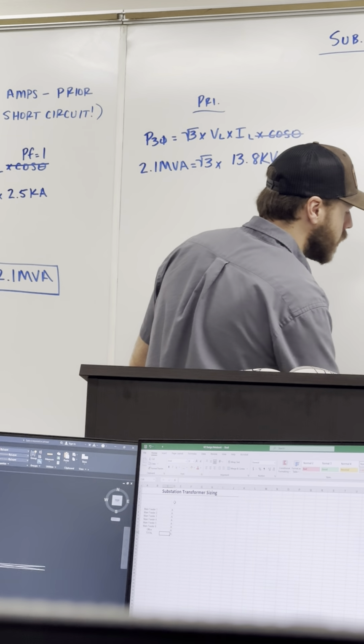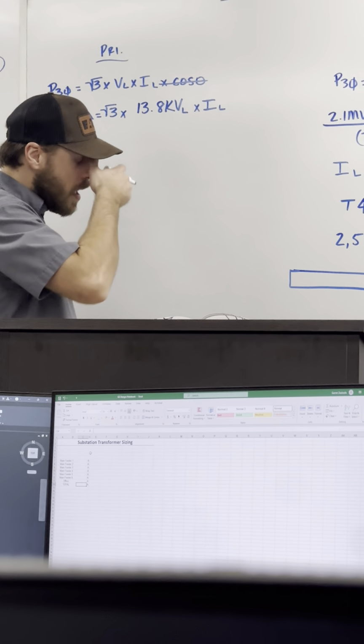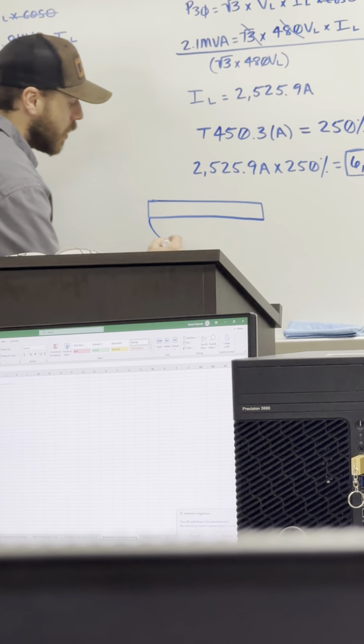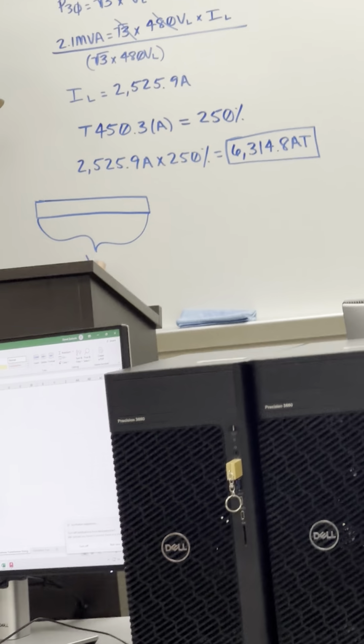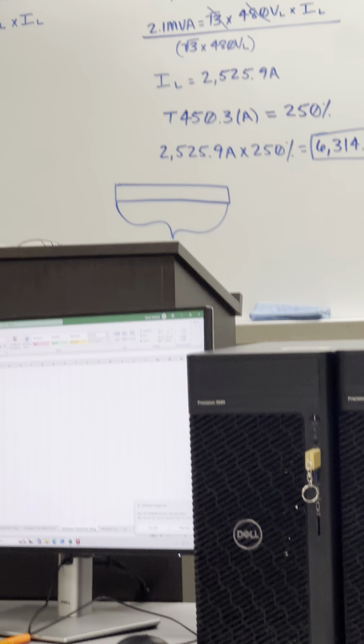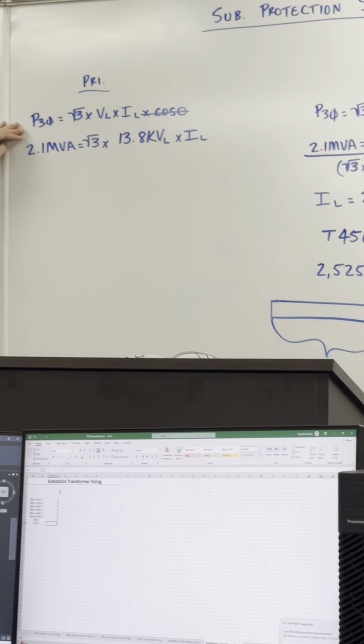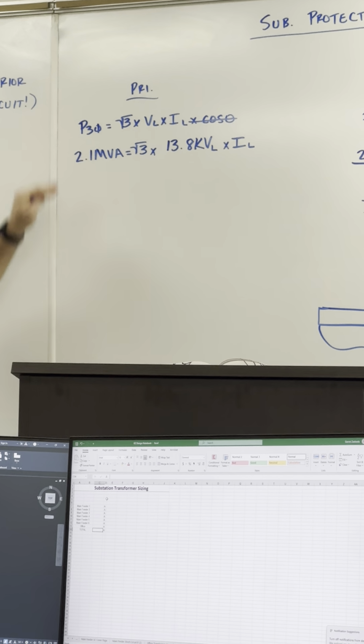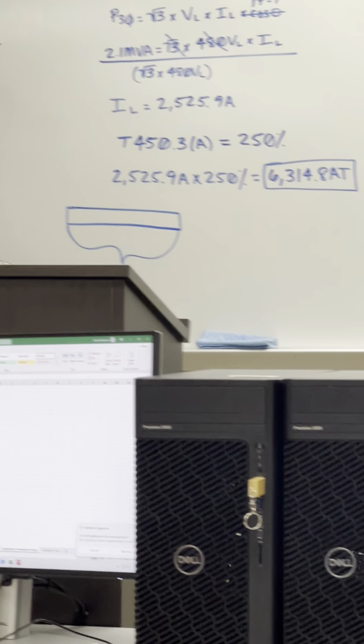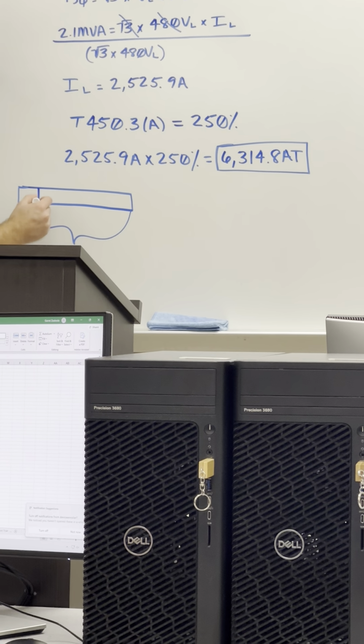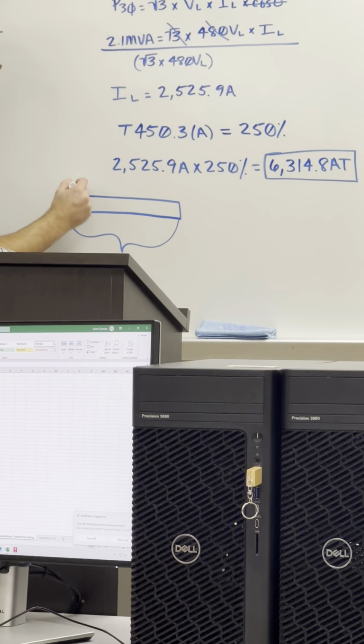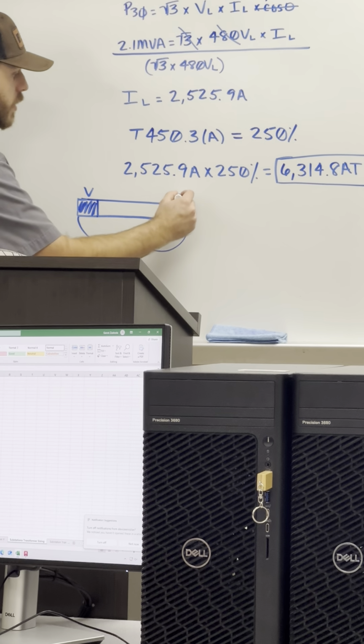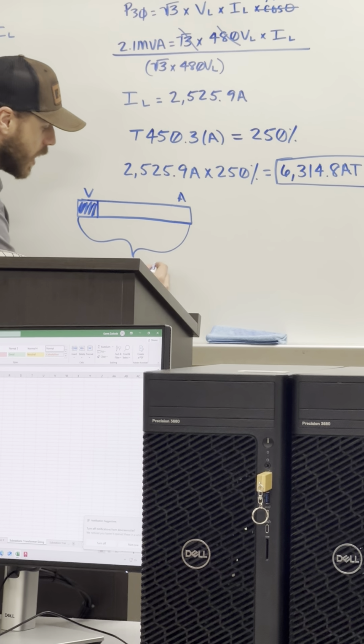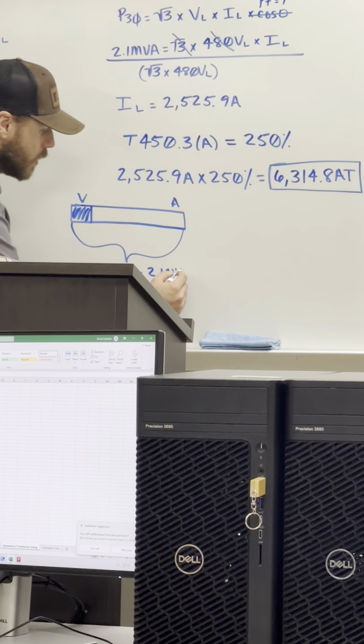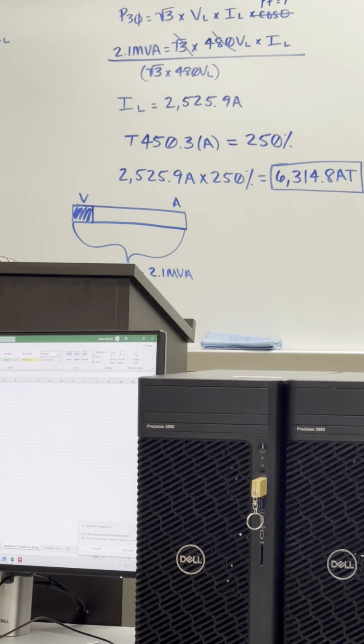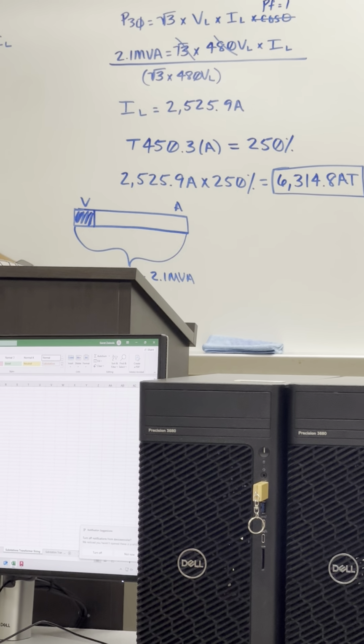So I kind of draw my little bar graph here. If we're drawing a bar graph, and this bar graph is watts, using Watt's law, because this three-phase equation here is basically just three-phase Watt's law. Well, on our secondary side here, we have 480 volts, so that might be that little shaded portion there. So our watts, in this case, is that 2.1, what we're calling MVA, because watts and volt-amps are the same. So that's our transformer size.